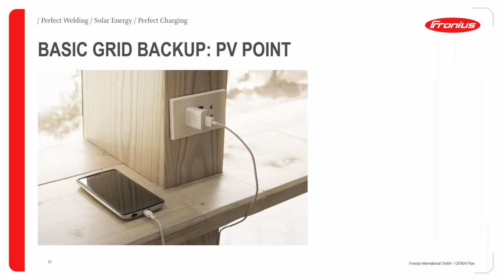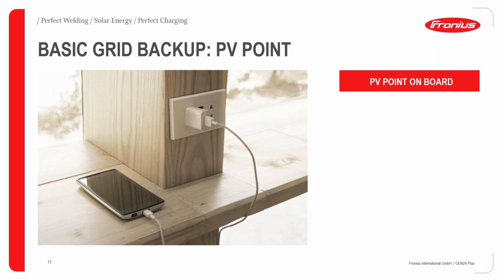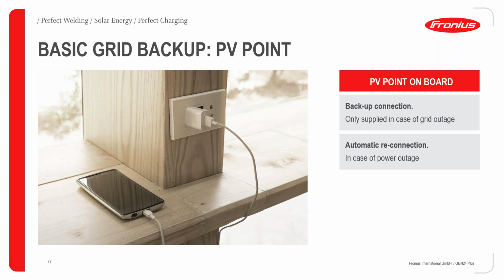The PV point is basically a basic grid backup already installed and available with the overall package of the GEN24 inverter. It's integrated as standard, on board the GEN24, and it's a single phase outlet where you can connect a cable to a wall socket, for example, like pictured here. This outlet, the PV point, is only supplied during a grid outage, with automatic reconnection. So if the grid fails, it automatically switches on to this PV point after a few seconds delay.